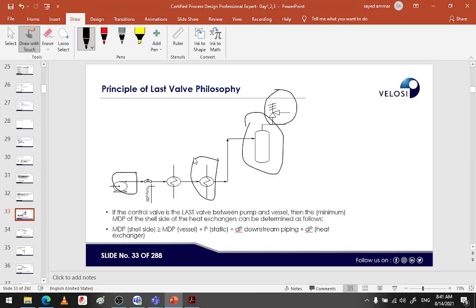Well, this one will be higher than the shut-off pressure of the pump, and this one will be the lowest one. The control valve here is going to reduce the pressure of the, let's say, pump discharge, and it will be reduced by the effect of this control valve to be whatever for the vessel. When we are going to design the shell, we are going to design for this one, because if we design for this one, we will pay a lot of money, especially if you are an EPC contractor. That's one of the tricks for the EPC contractors. He designed for the vessel, he did not design for the shut-off of the pump, by allocating this valve here.